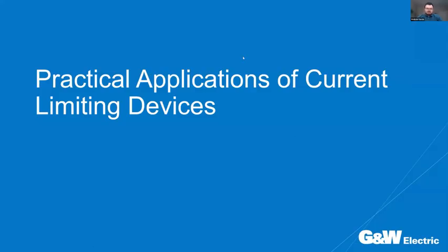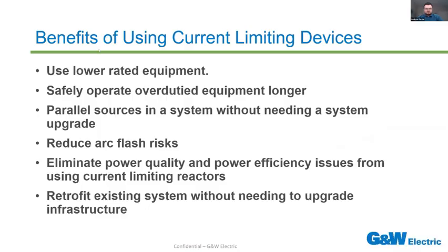So what are some practical applications they can get into with current limiting devices? Just going over the benefits of why you would use these. You can use lower rated equipment by lowering the available fault current. You can use lower rated equipment, save some money, or keep your project on track if you find out currents are higher than expected. If you have an already existing facility, you could safely operate any equipment that you find is overdutied for a longer period of time without some kind of expensive retrofit.